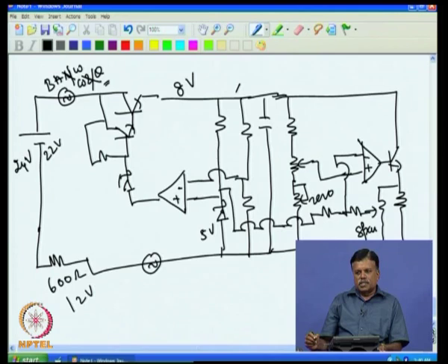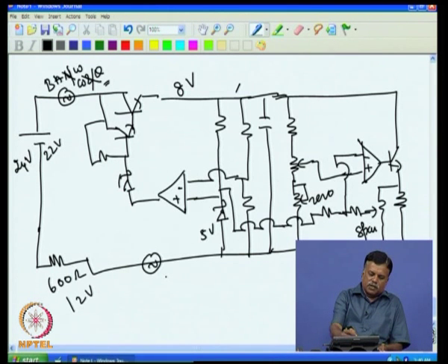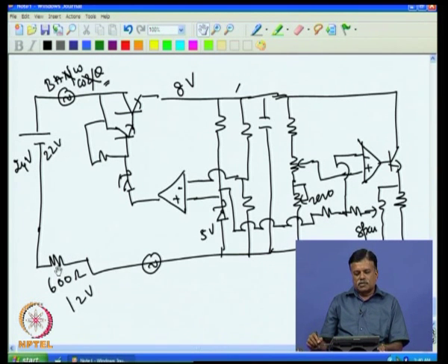That is why this current transmitter is used, and also only 2 wires are used. In practical usage, we find that there is no problem because of the noise, and we need not put too many wires, because the wires have to be long. Too many wires will cost more money, so that problem is also solved. Even a small change in the voltage, or a load change or wire resistance change, will have no effect on the signal here. That is how these 4 to 20 milliampere current transmitters are made, and they are used in the industry.